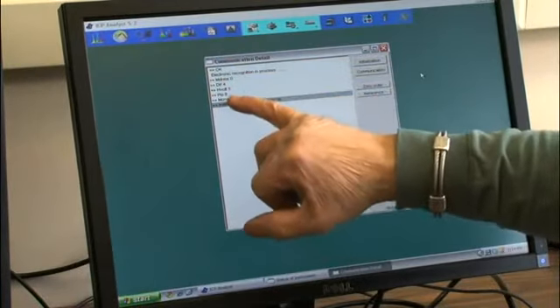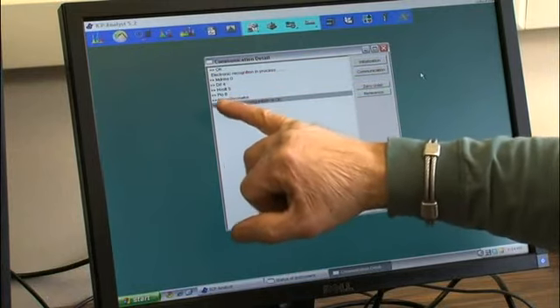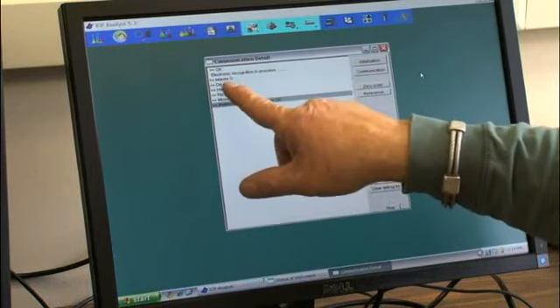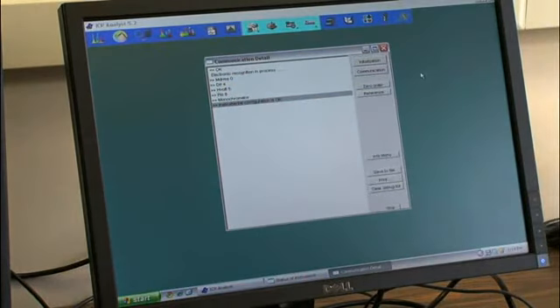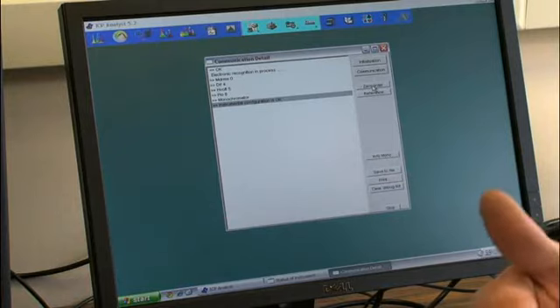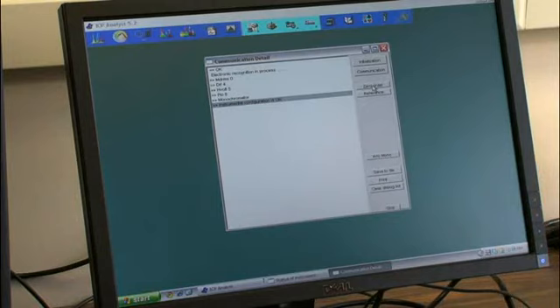You should have 4 boards: your high voltage, your PIO, your diff, which is actually called acquisition in there, and the MDRMS, which is the one that moves the grating. First thing we do is a zero order, and what that does is it moves the grating so it's parallel with the mirrors and it doesn't split up any of the white light. So it's looking at all the white light. That's the initial starting point, and you only need to do that if you lose the reference.